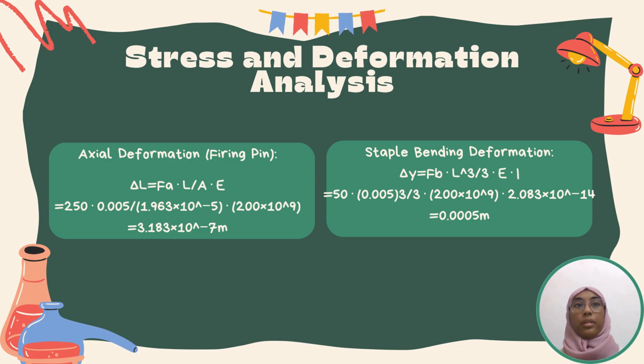Lastly, we use stress and deformation analysis. We evaluate stress and deformation in the stapler's components under different loading conditions: axial deformation of the firing pin and bending deformation of staples. However, for bending, minimal deformation was observed, underscoring the importance of material properties in resisting bending stresses. Through this, we identified areas where material improvements could enhance the stapler's reliability.